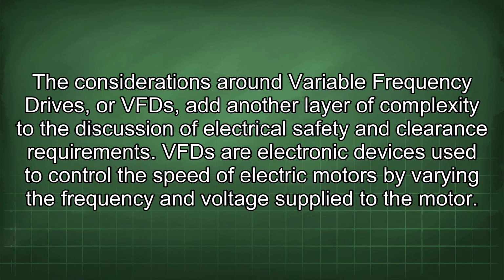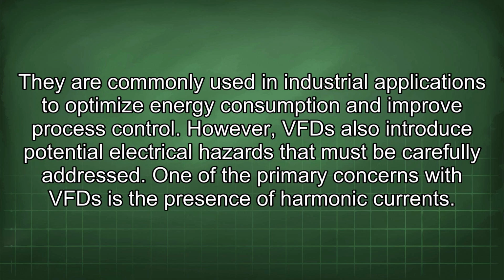and clearance requirements. VFDs are electronic devices used to control the speed of electric motors by varying the frequency and voltage supplied to the motor. They are commonly used in industrial applications to optimize energy consumption and improve process control. However, VFDs also introduce potential electrical hazards that must be carefully addressed.